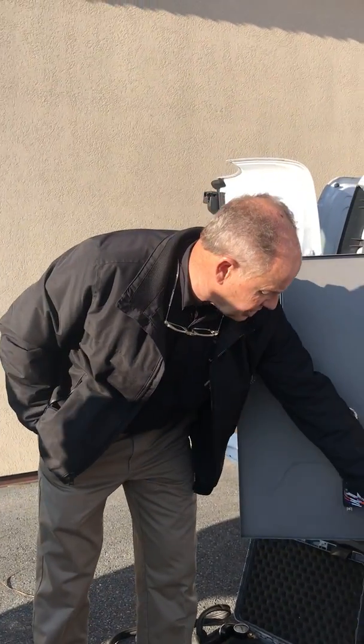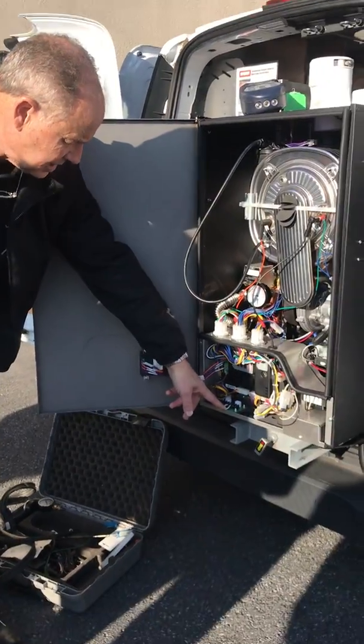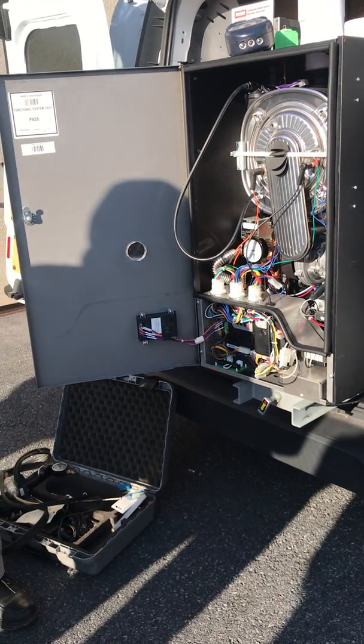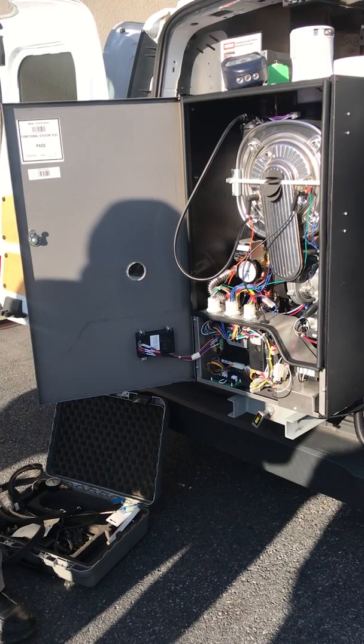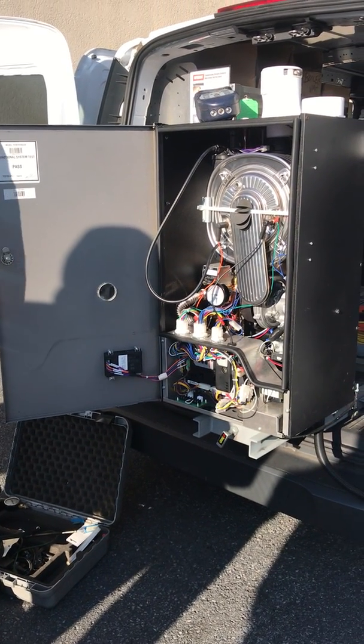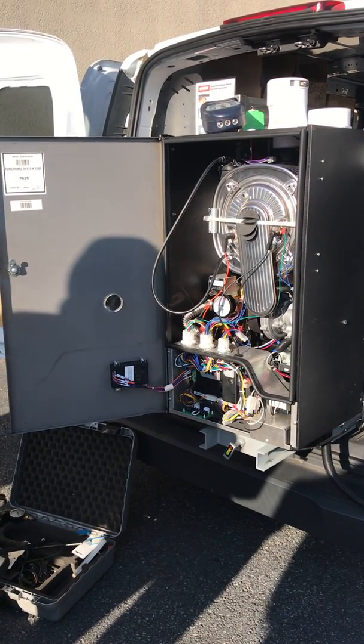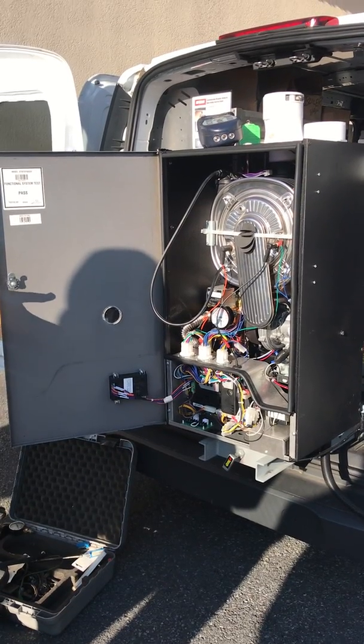This has your low voltage connections. There's a connection in here where you can put your limit circuit. I can put my low water cutoff. Do you put low water cutoffs on each one? Not now. Okay, there's a flow switch in here.